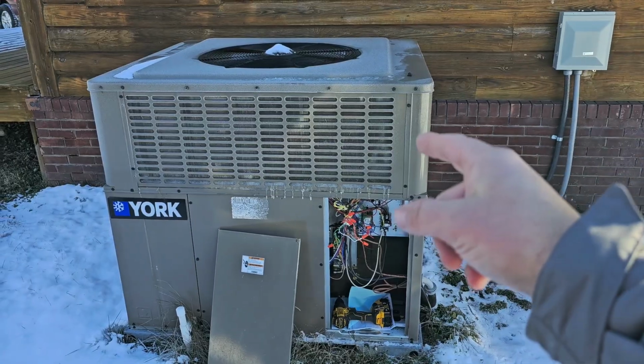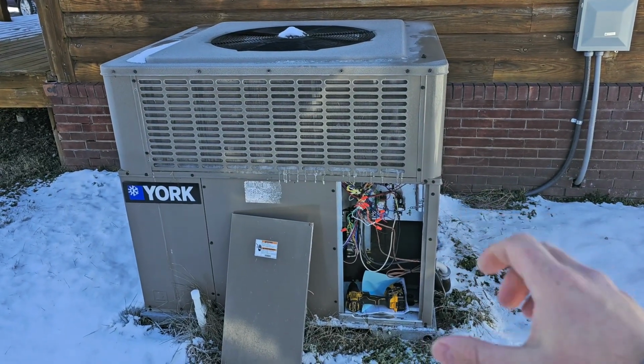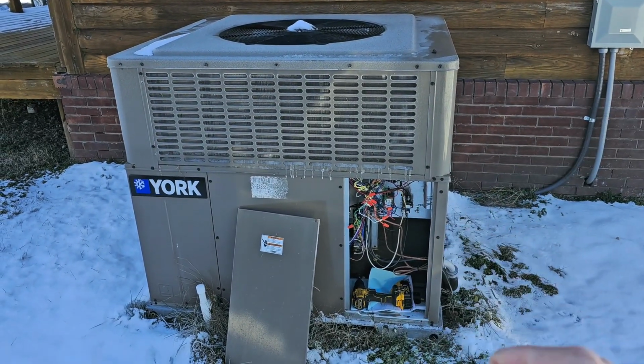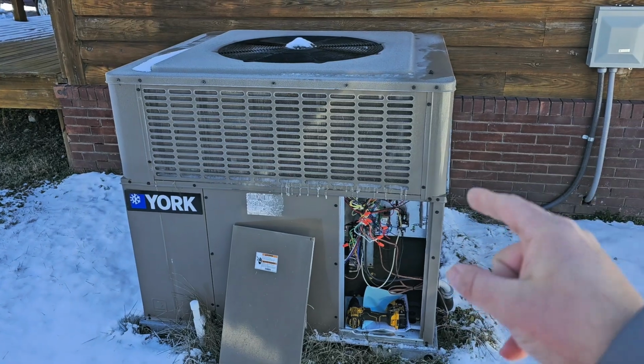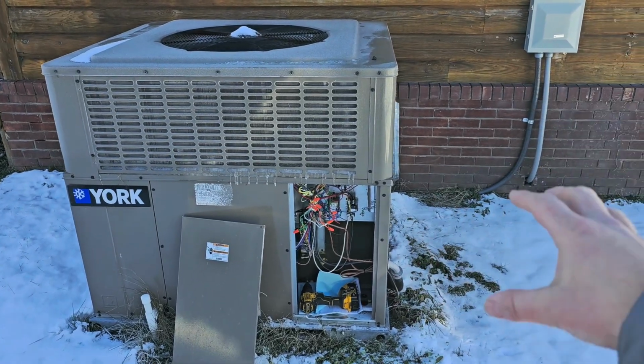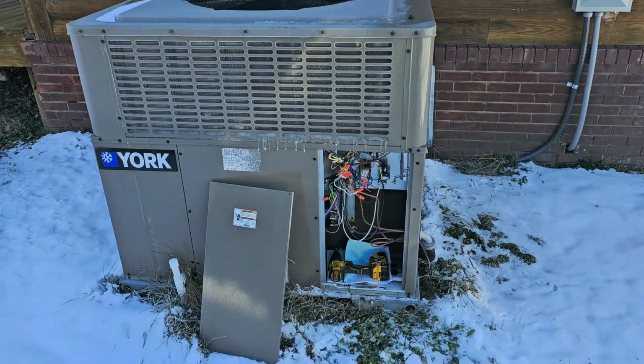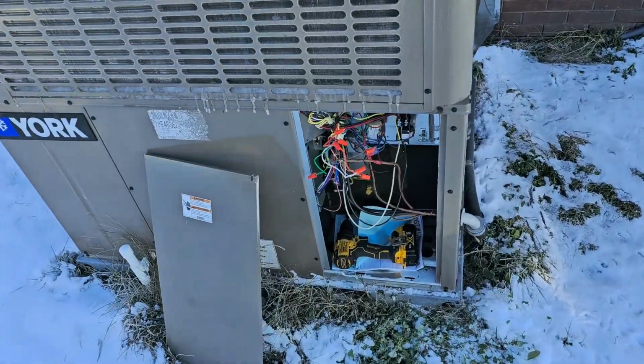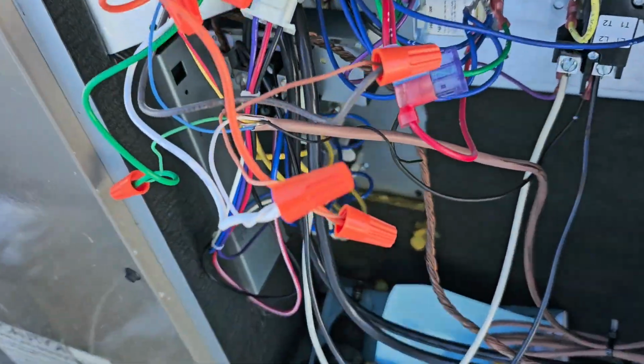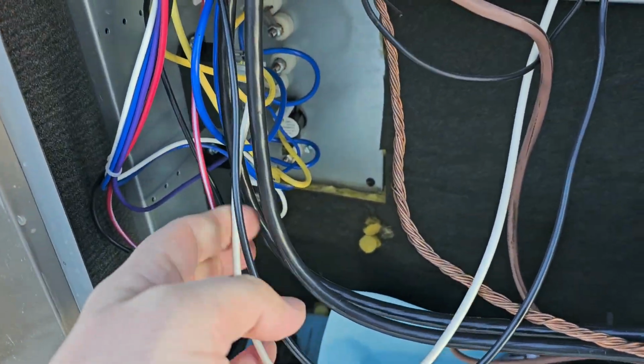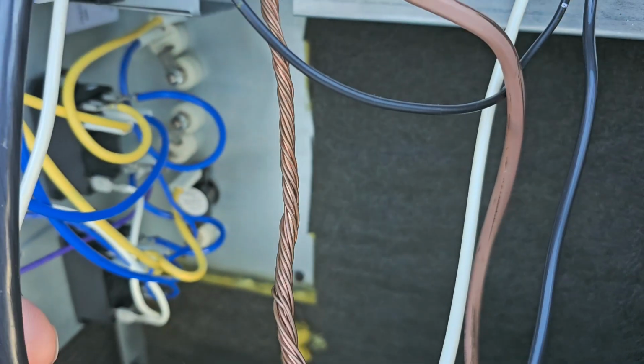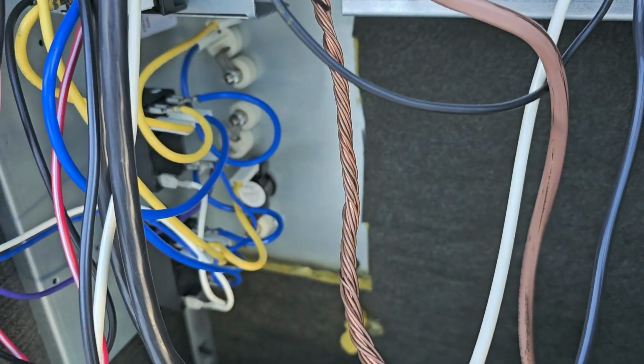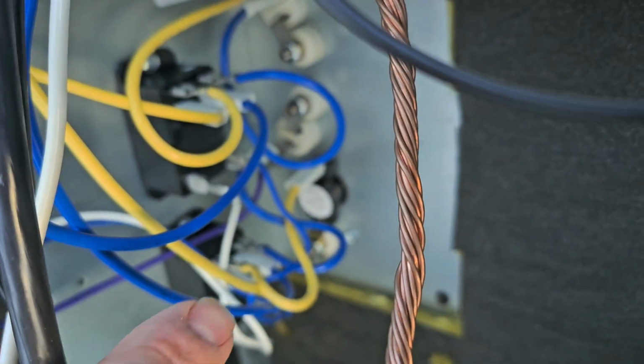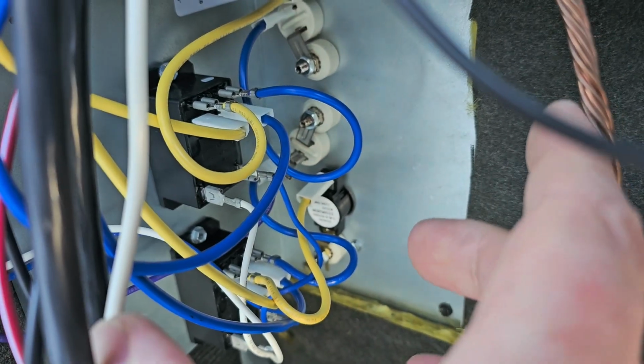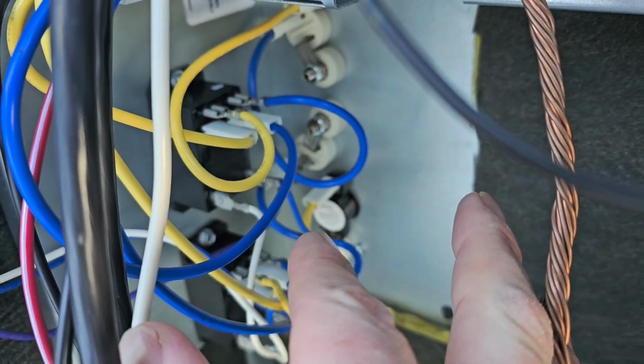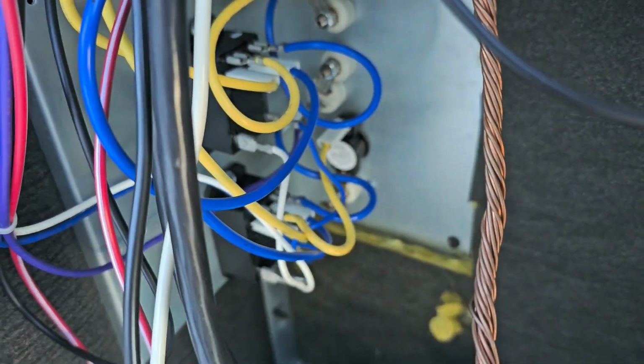This is called a package heat pump. It's all outside. There are package heat pumps and there are split heat pumps. You may have a split heat pump. That means part of it's outside and part of it's inside. And your emergency heat, if you have a split unit, is on the inside of the house, maybe in the basement or the attic. Since this is a package unit, our heater kit or electric heat strips, otherwise known as emergency heat, is right here. So that's what emergency heat looks like.